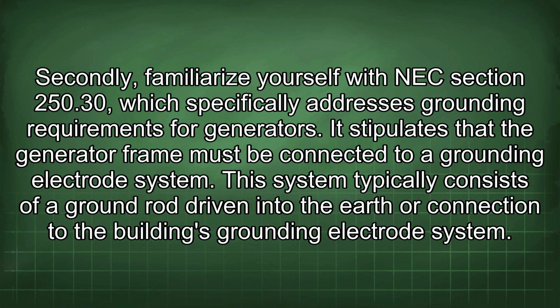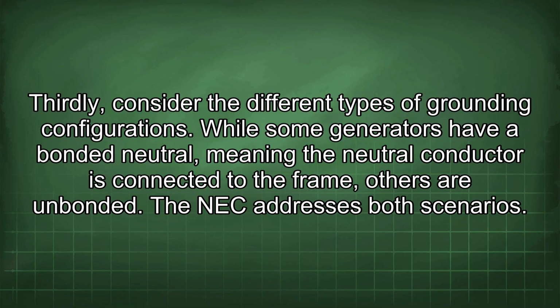It stipulates that the generator frame must be connected to a grounding electrode system. This system typically consists of a ground rod driven into the earth or connection to the building's grounding electrode system. Thirdly, consider the different types of grounding configurations. While some generators have a bonded neutral, meaning the neutral conductor is connected to the frame, others are unbonded. The NEC addresses both scenarios.